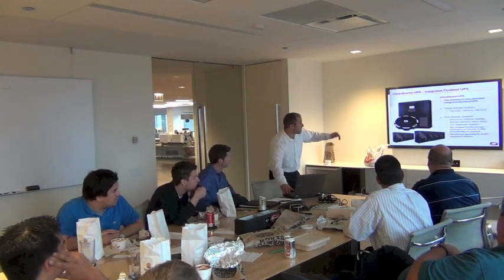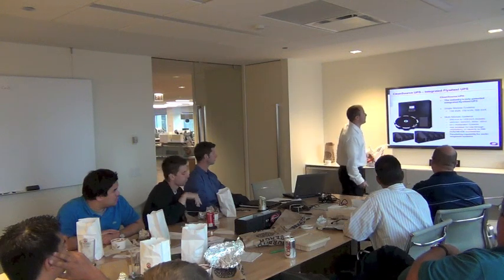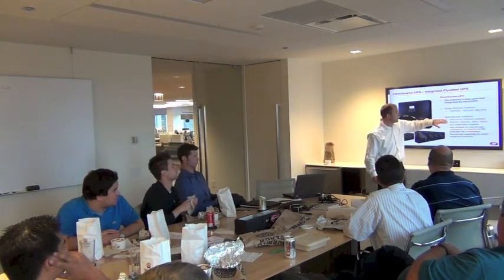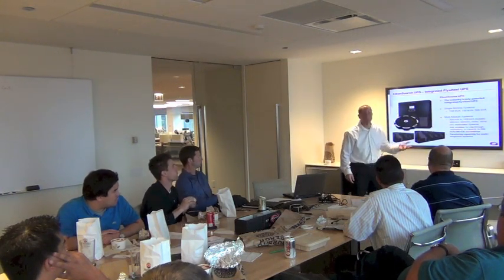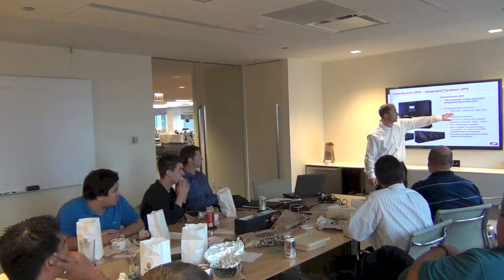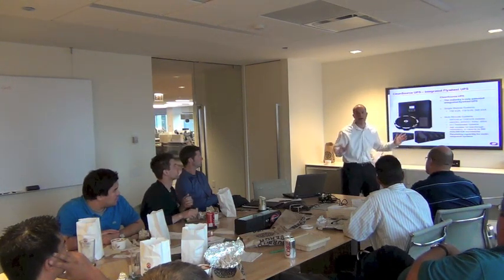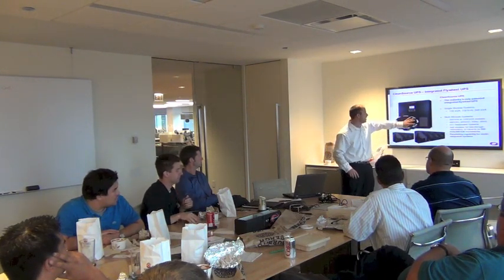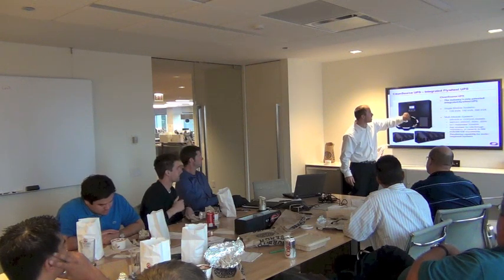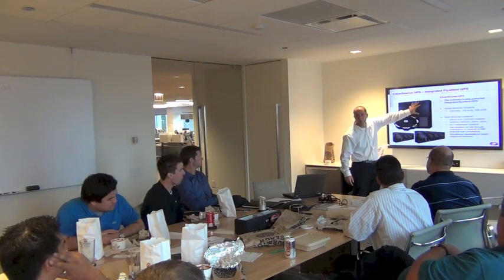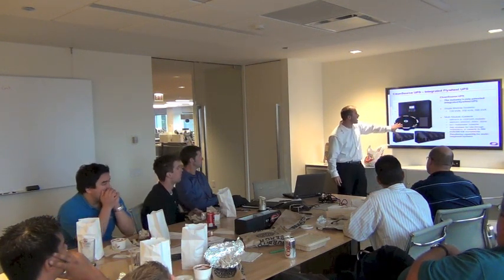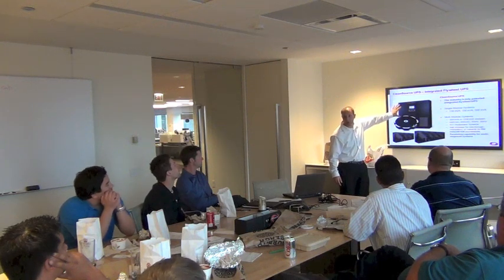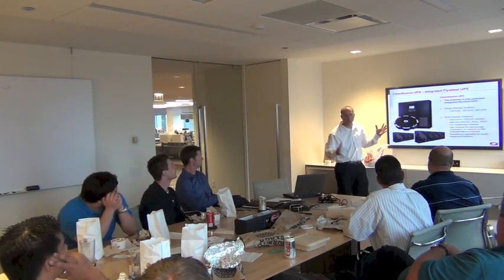Again, we have what's referred to as a single module system, and then a multi-module system. So really two main frames. The single module system is 130, 150 to 300. It's non-expandable. It's basically a one-box system. You have your flywheel energy storage in the bottom and your power electronics towards the top. You have a side cabinet with an option for a 3-switch maintenance bypass. So it's just a nice one-box solution.